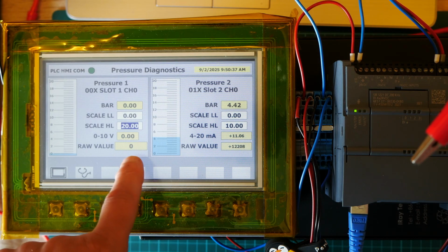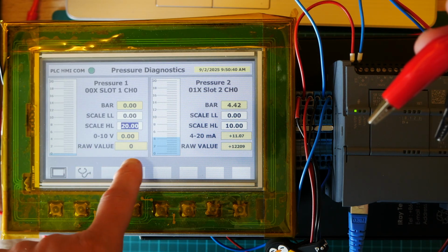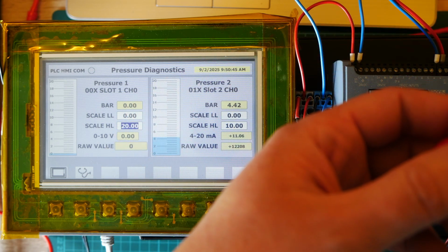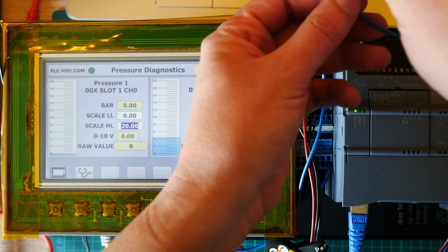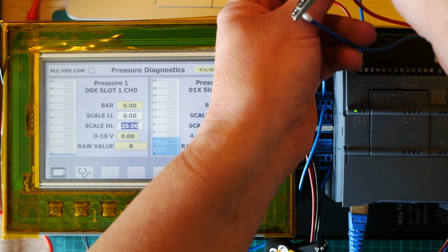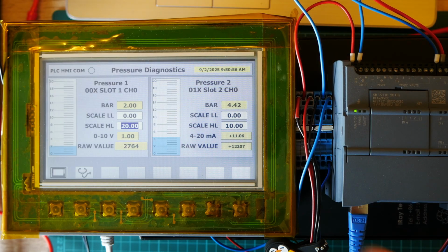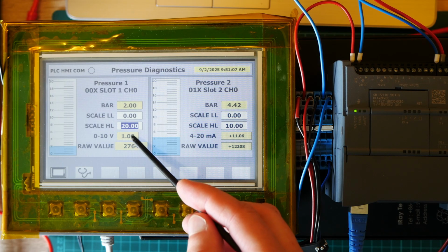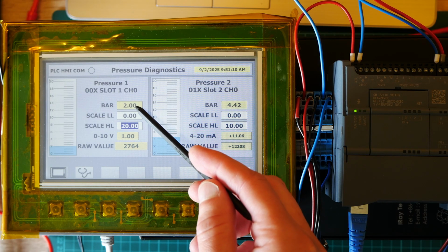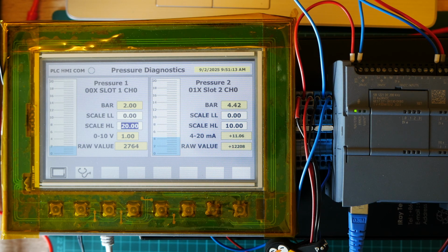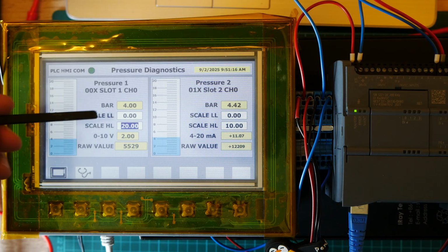So the sensor is disconnected, it shows raw value as 0, yes. And you connect your bench power supply to this analog input, and you sweep the range. Okay, so from my bench power supply right now I'm outputting 1 volt to the input card, it shows 1 volt here, and we have 2 bars. If I output 2 volts, I have 4 bars.